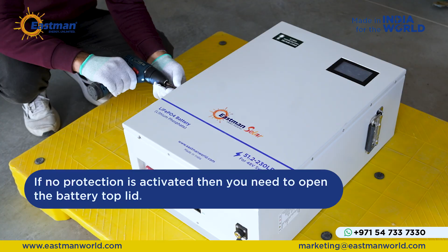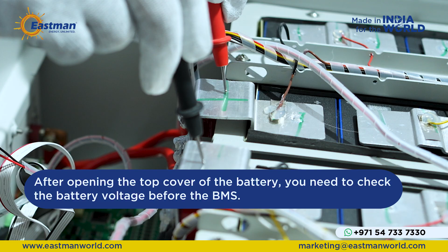If no protection is activated, then open the battery's top lid. After opening the top cover of the battery, check the battery voltage before the BMS. Using a multimeter, check the overall pack voltage before it enters the BMS.